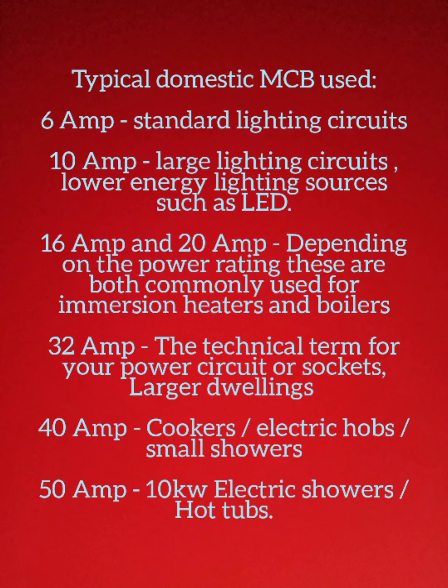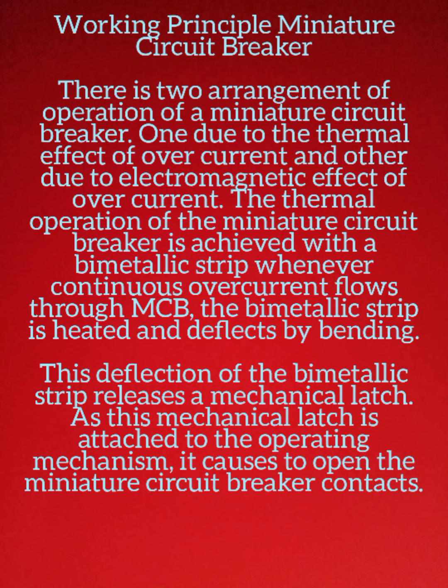So the MCBs can be used up to 125 amps. Normally the short circuit withstanding capacity will be 6000 amps for domestic use. For industrial it will be 10,000 amps.